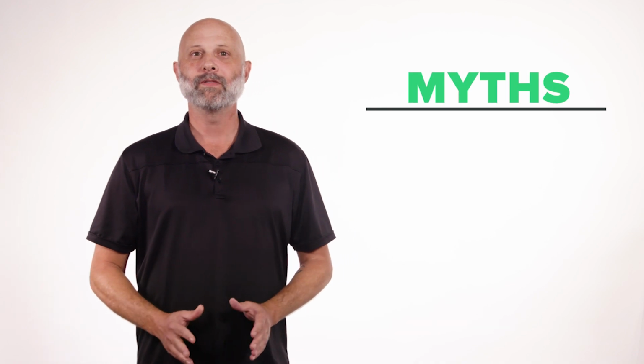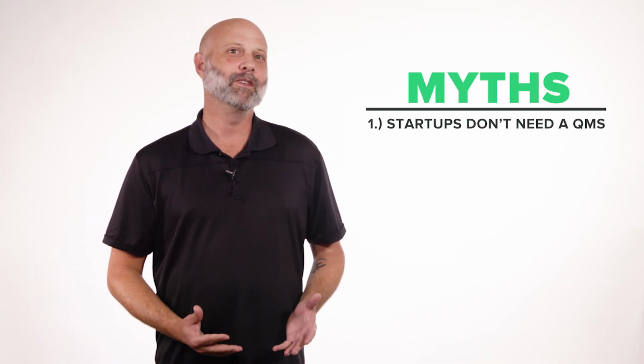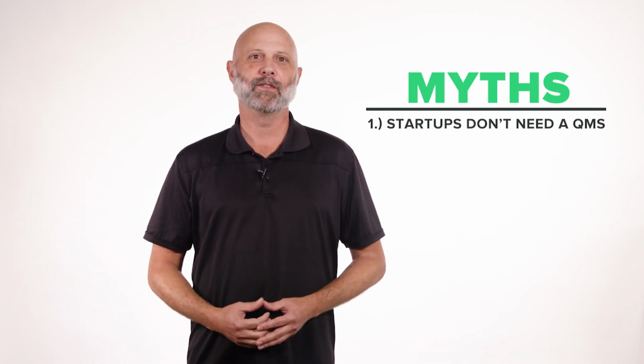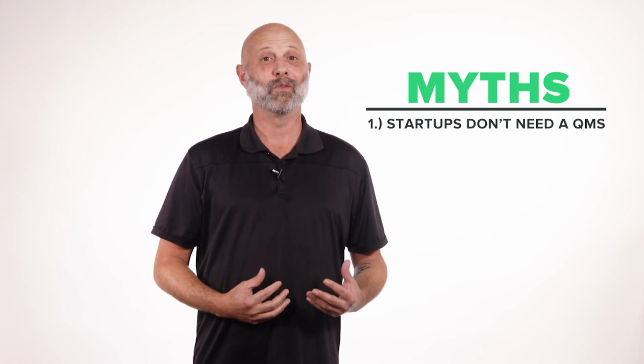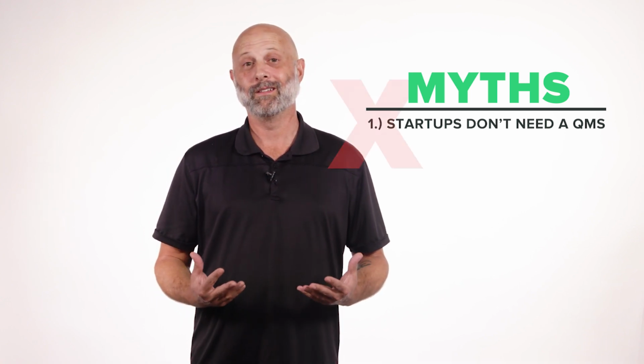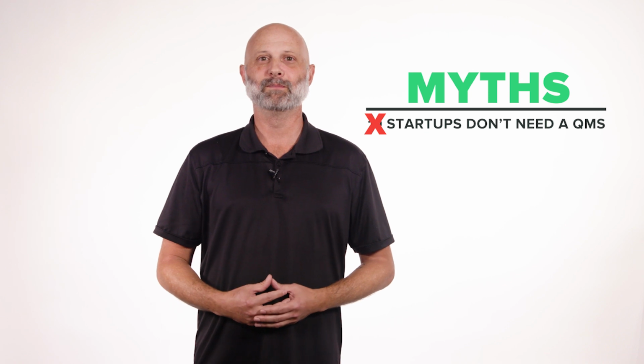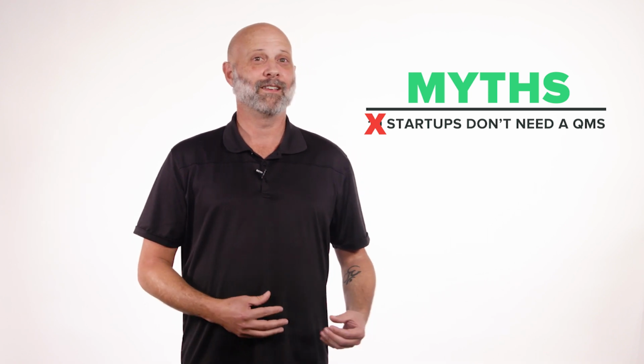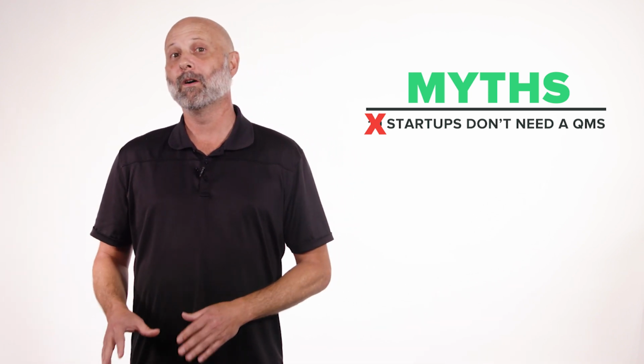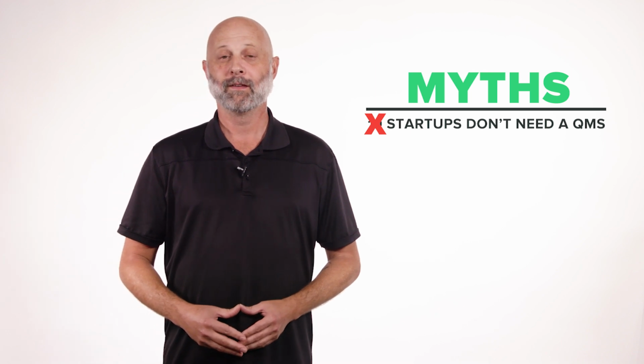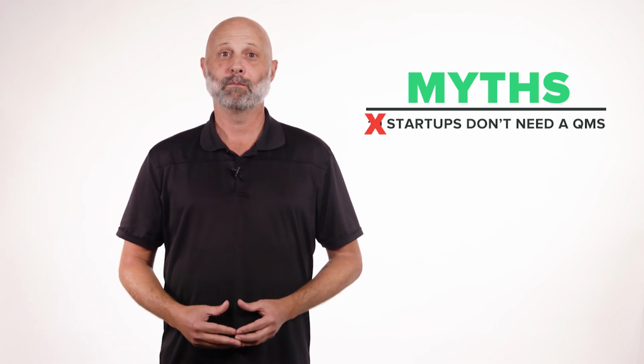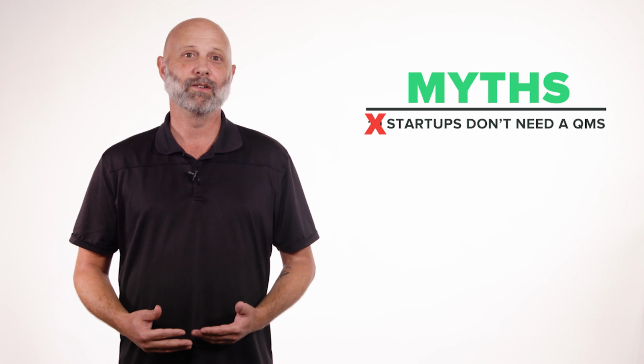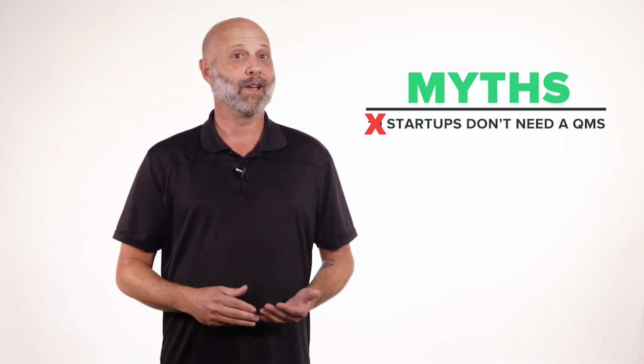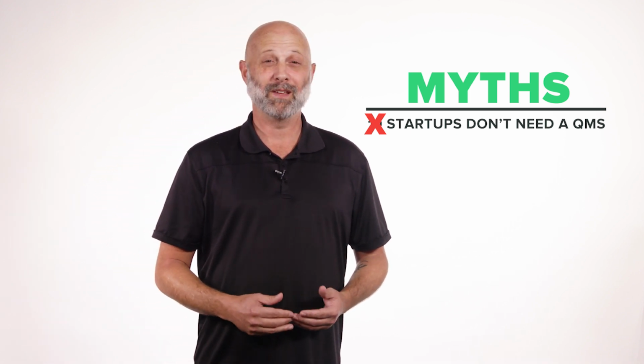Myth number one, startups don't need to implement a QMS until they've received regulatory clearance or approval. Well, frankly, that's wrong. It's important to implement certain key processes of your QMS early on in the design and development phase. Make sure you establish processes around managing your documentation, your design controls, and risk management at the very least.